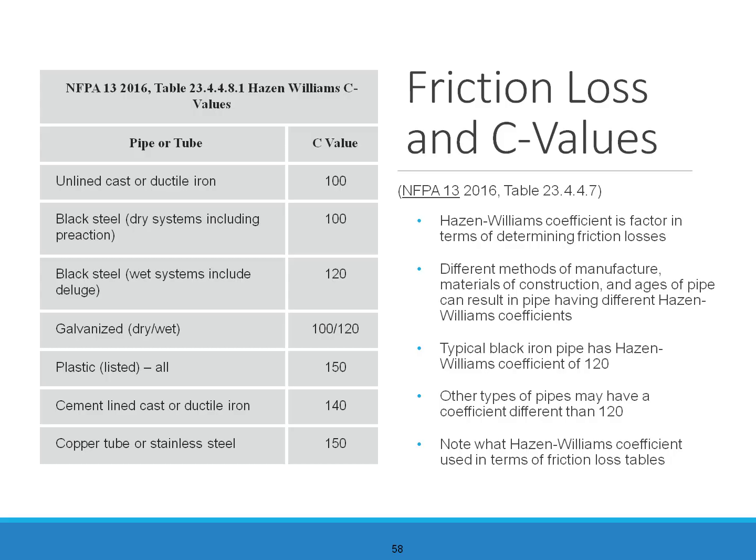Table 23.4.4.8.1 is the Hazen-Williams C-value table. So for an example, black steel for wet systems including deluge is 120.